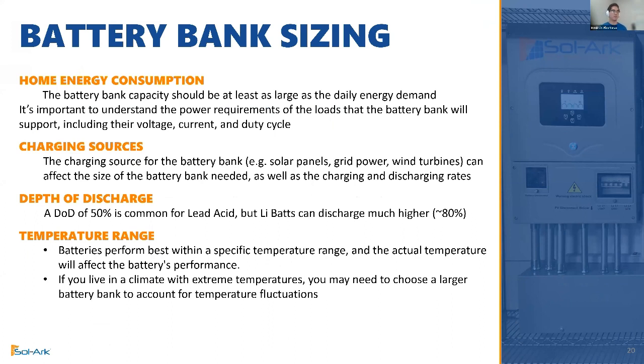know what the home energy consumption is going to be, right? So the battery bank should be at least as large as the energy demand that the home takes daily. And of course, it's important to understand these power requirements because it will affect the way the system works. And so you need to know essentially the voltage, currents, and duty cycles of those loads. For the charging sources, that's also extremely important in terms of your battery bank. So you want to ensure whether you're going to use solar panels, the grid, maybe a wind turbine. These all can affect the size of the battery bank and also the charge and discharge rates. The depth of discharge is also an extremely important factor for choosing the battery bank size. And so lead acid does commonly have a depth of discharge, or DOD, at 50%, which is not essentially the most efficient in terms of usage.